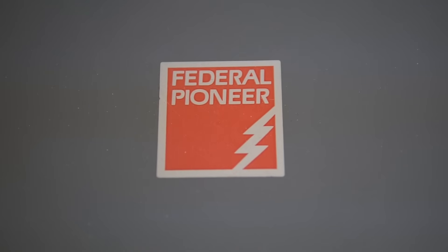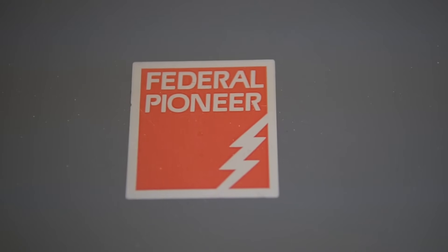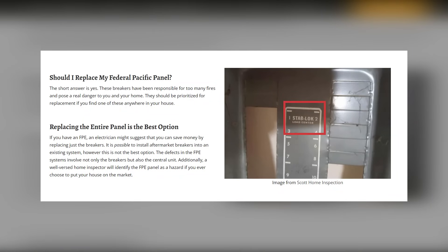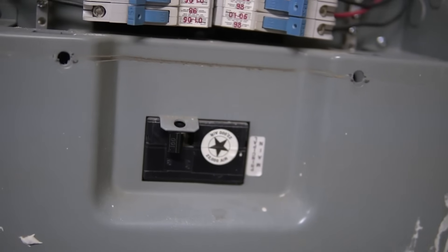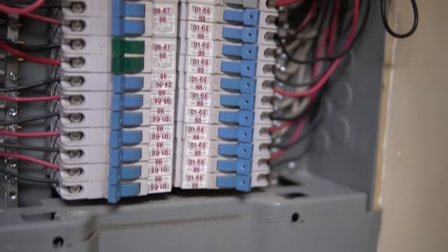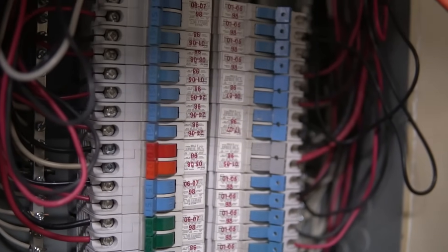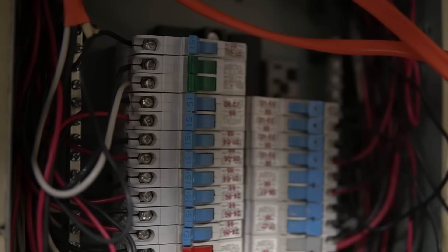And then unfortunately, when it comes to the breaker panel that I have, which is Federal Pioneer, it is known for not tripping properly and it might catch on fire if you use too much power on that panel. So if you have the same one, then please be careful. And if you're not experienced with any electricity stuff, please contact an electrician.